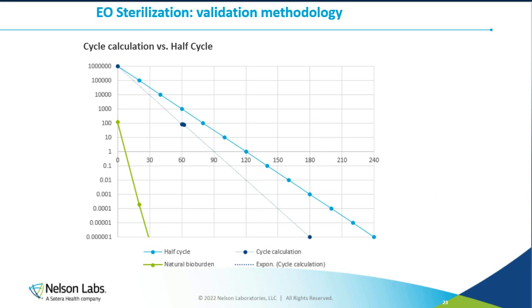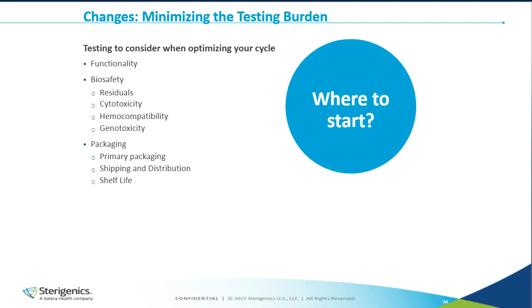By switching from one method to the other, we can also reduce the duration of a cycle. So a combination of a more appropriate PCD selection, as well as an alternative technology or methodology for validation, can save a lot of time and concentration, without changing, I would say, too much the cycle parameters. If I am changing my cycle, of course, it will bring a lot of questions. We need to evaluate whether it has an impact on the functionality of the device, because it has to be sterile, but it still has to work. So functionality is a key element to review.